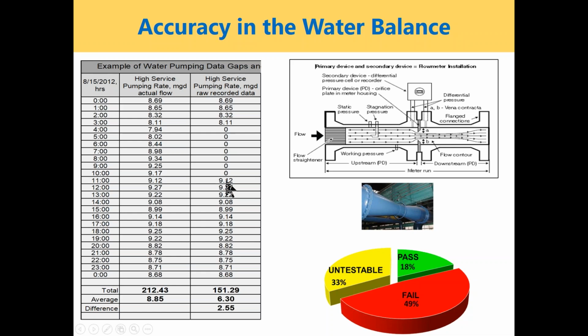This one's from Philadelphia as well, where from 4 to 10 o'clock there was an interruption in the comms, probably a lightning strike or storm. As far as the pump knew, everything was churning like it should. But as far as SCADA was concerned, there was no water produced between 4 and 10, and that's what got archived into the history and archives within SCADA.